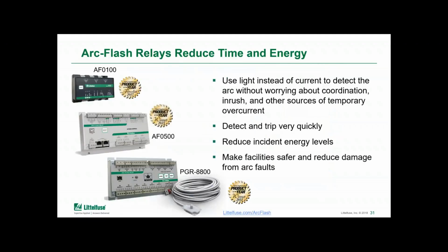This shows a few examples of arc flash relays, which are designed to use light instead of current as the primary measurement to detect the arc. Each of those products has the ability to detect and trip the breaker quickly. If there is some concern about high intensity flashlight or other things like that in the equipment, because these relays use light as the primary trigger, you can also take phase current measurements and bring them into the relay and program it to use both light and current as your threshold before taking action.